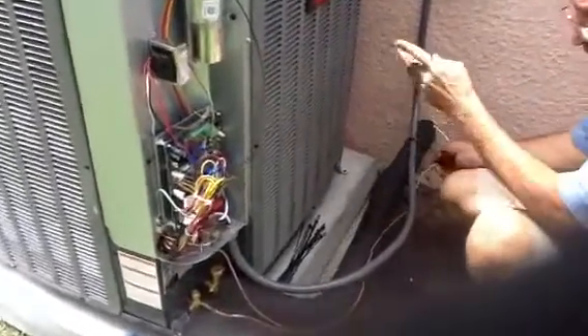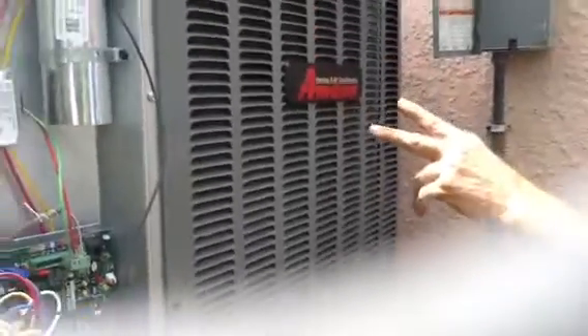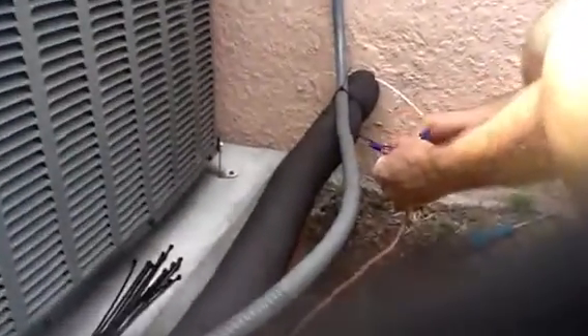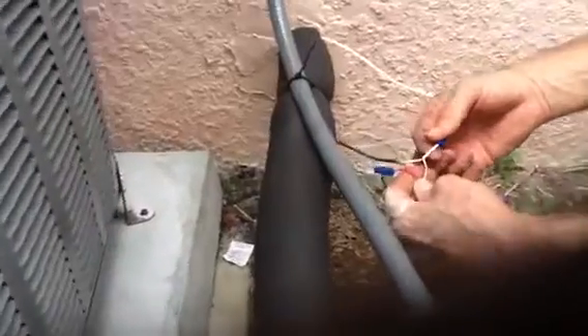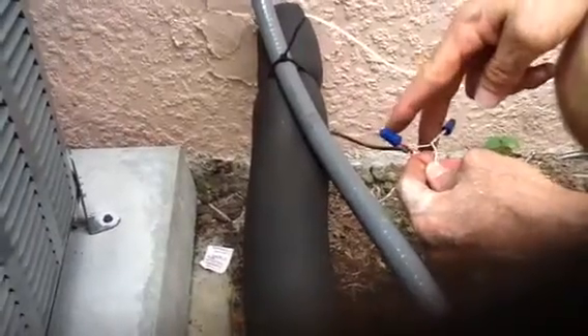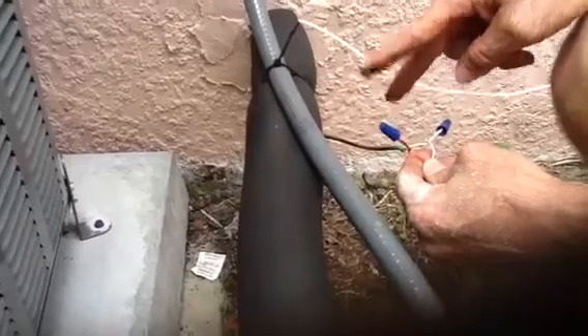Today we came back to put a Amana communicating system in. I'll talk about the thermostat later, but it takes a four-wire system for these communicating systems. Here's the original wiring — he only had three wires. So now we have a problem: we need four wires and we've got three. We're going to use two wires as our low voltage wire, like you would a standard condenser going back to the air handler.